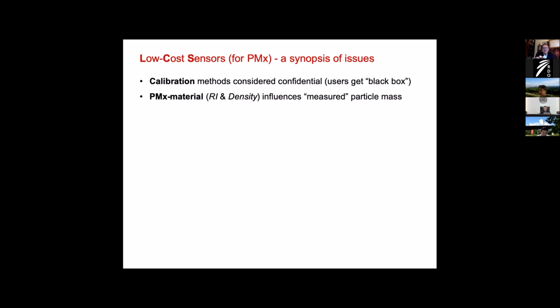So the problem with low-cost sensors is we are getting a black box. We have no idea if it was calibrated and how it was calibrated, if at all. If we measure with low-cost sensors, we don't know what material we are measuring. We can estimate: when we know it's more soot particles, then the density would be somewhere around 1. If we think these are probably particles coming from some mining area, well, the density will probably be between 2 and 3. We also don't know the RI, the refractive index, which also influences the measured mass.